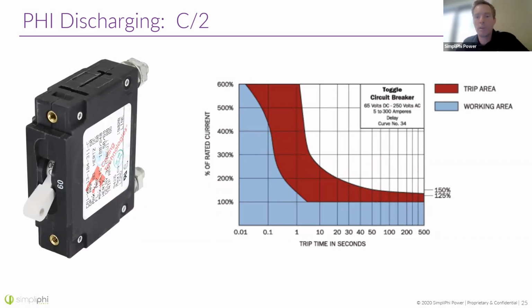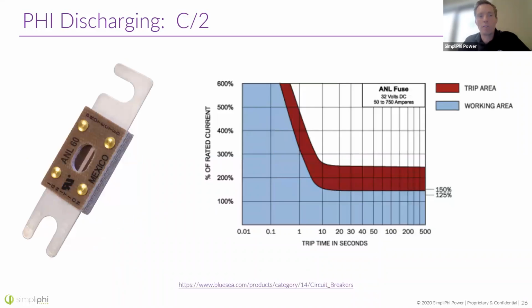Here's another breaker, and you get this time graph as well. This one should trip after 1.5 seconds, right at 100 amps. So when you buy breakers and you're using them to protect equipment, it's important that you look at the specifications on the breaker itself. This one, if I hit 200% of the required load, it doesn't take 10 seconds. It takes about 0.4 seconds or so for this to do it. And this is on a log scale on the bottom. So it's a little bit different looking at this one. But again, check the specifications of your breakers as you're looking at them.